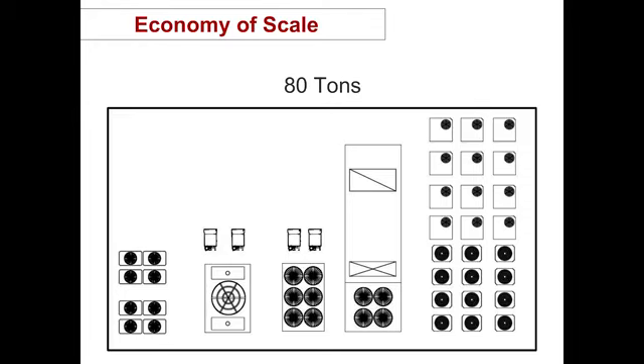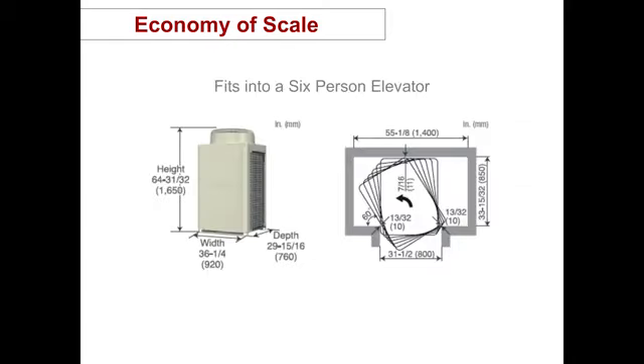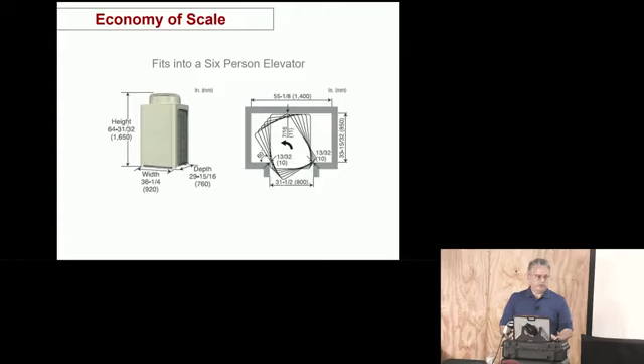So the scale of economy, if you're looking at it in terms of roof space, to the right here we have RTUs, and these are condensers here. And this is a chiller system. This is an air-cooled chiller, water-cooled chiller, and this is 80 tons of VRF. At one time, there was an outdoor unit, and there may still be, of this size, of this chassis, that can fit into an elevator. And if you're doing a retrofit, that could be pretty helpful.